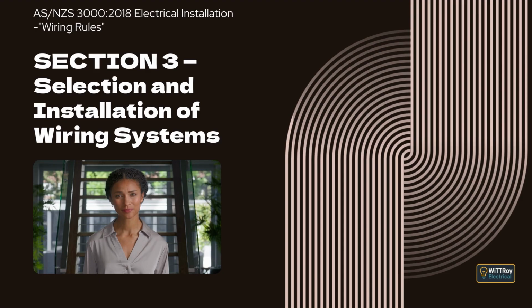This clause explains that joints in cables must normally be enclosed to protect against external influences, unless specific conditions are met, such as no undue strain, compliance with connection requirements, reinstated mechanical protection, and restored insulation and sheathing equivalent to the original cable. Clause 3.7.4, Installation couplers. This clause explains that installation couplers complying with AS/NZS 61535 may be used as a permanent connection method for cables, are considered equivalent to a junction box, and are not intended to be connected or disconnected under load.